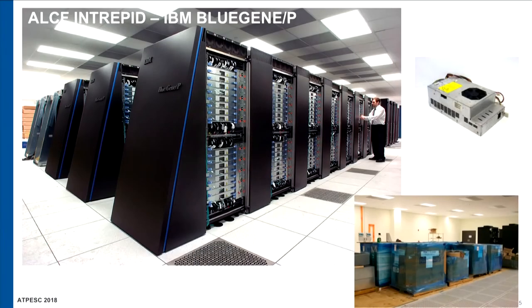These are 480 volt systems, and you really don't want exploding things in your 480 volt electrical system. While we were working out the issue, it turned out to be a cheap capacitor they had put in that couldn't stand up to the loads we were putting on it, and was a little too close to other components on the board in the bulk power module, causing them to pop.